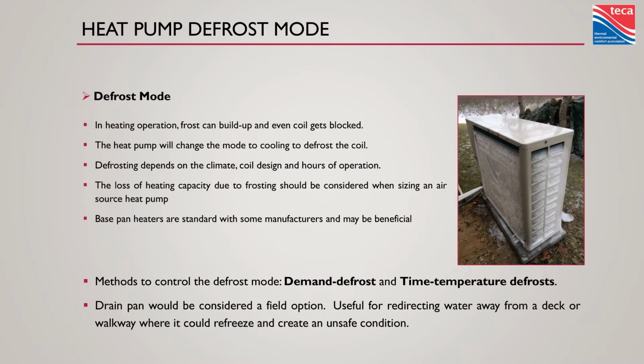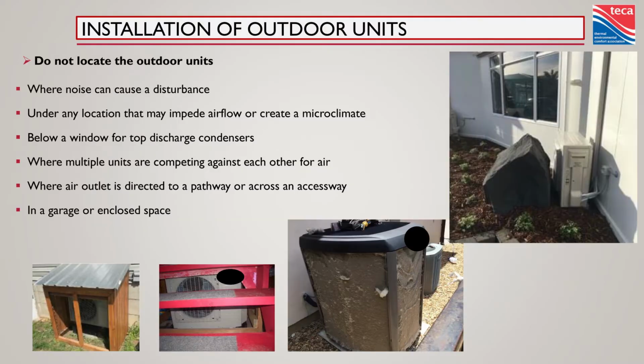In fact, the more efficient the heat pump, probably the quicker it's going to frost up. It's a good thing. Look at how good a job it's doing of taking heat out of that air. It froze. It's great. It's not a bad thing. Just hopefully it does it quickly. So it looks like that. You know, you might not have snow on the ground, but you got ice on the heat pump. Hopefully it terminates quick. There's a few different modes for that. Try not to do some things. You know, sometimes you gotta poke some fun.